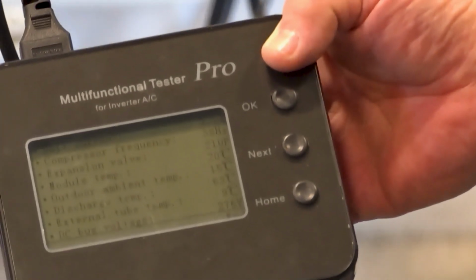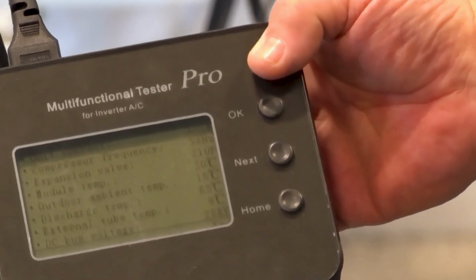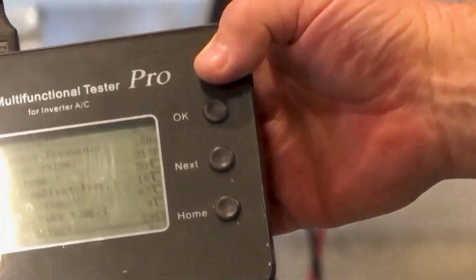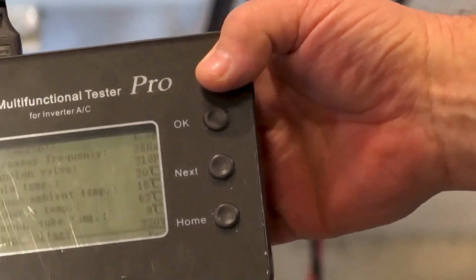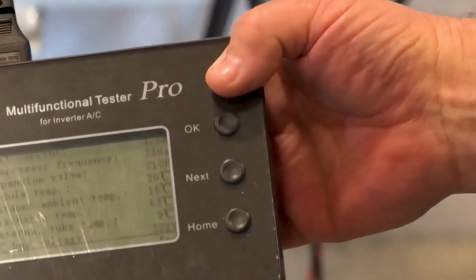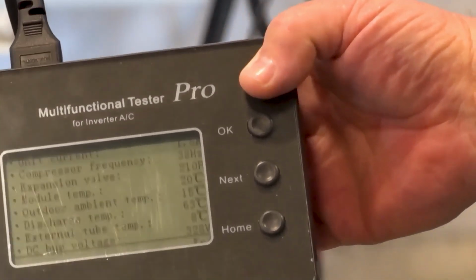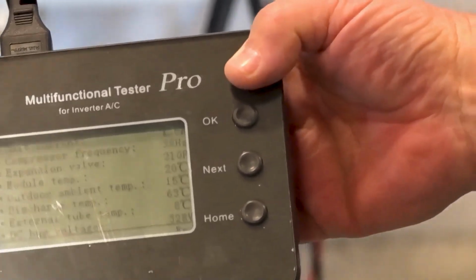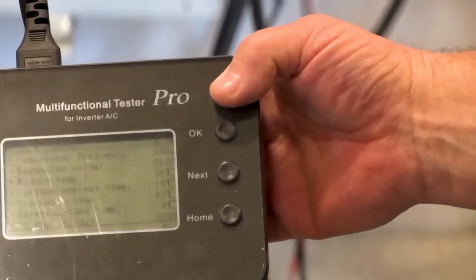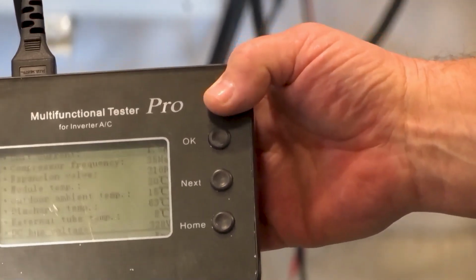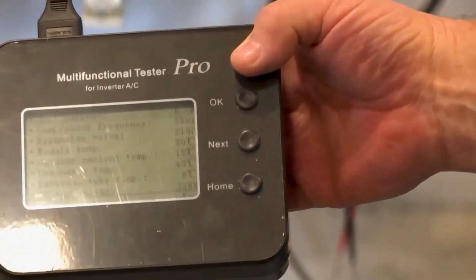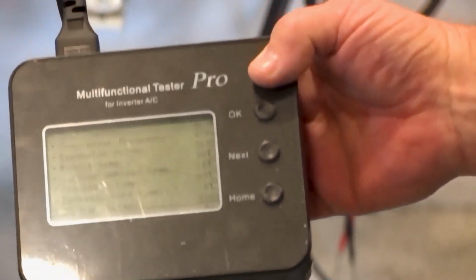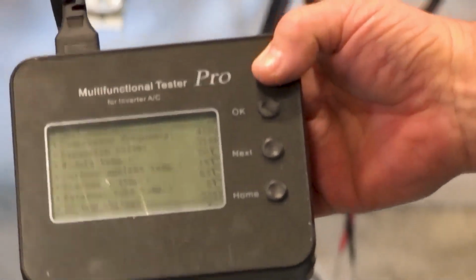So part of my experience with that is, remember when we were just talking a few minutes ago, I was talking about the multi-zone unit, and if you've got high discharge temperature, it's a good indication you're low on charge. Well, in my experience, I've dealt with machines where they were low on charge, and I'd run one indoor unit, my discharge temperature was pretty decent. And then all of a sudden I'd turn on the second unit, and my discharge temperature would go up even more. Then I'd turn on the third unit, and it would climb again. So the only thing I was doing was putting more demand on it. The unit was low on charge, which was causing my discharge temperature to go up.